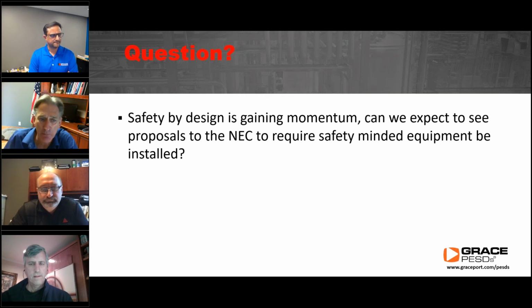There is a requirement in the 2017 edition for service equipment, and it's talking about in other than dwellings, in addition to A, which is the general arc flash label that just has to say warning, arc flash hazard, just some general generic information. Now you have to have a permanent label, field or factory applied at service equipment rated 1200 amps or more. In that section 110.16, there are specific requirements that have to be on that label. There is an exception though, if the label is like our arc flash label that we have in accordance with 70E, that is permissible instead of having the other information like the available fault current and the clearing time actually on the label.